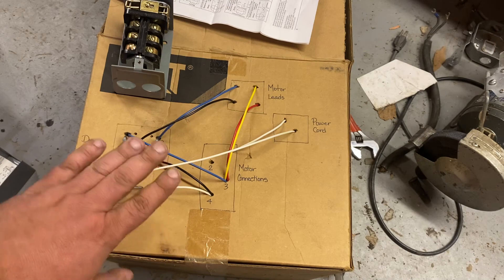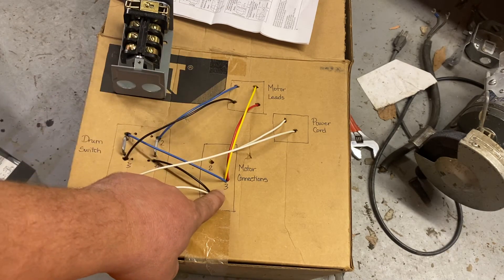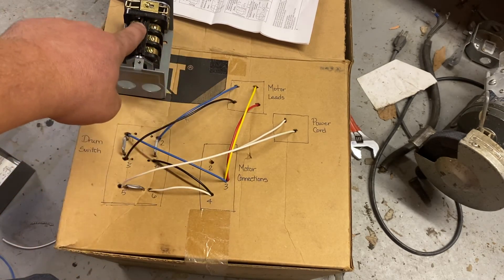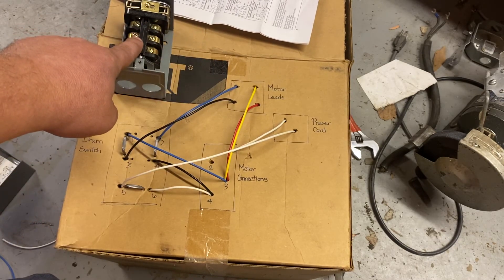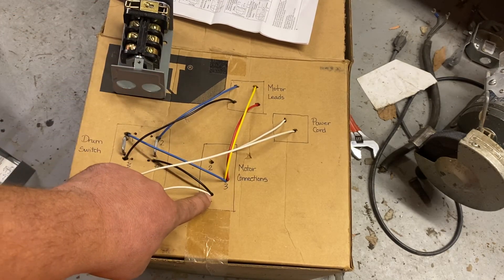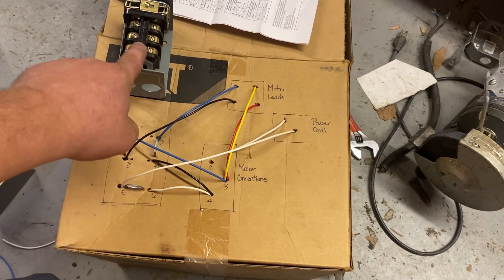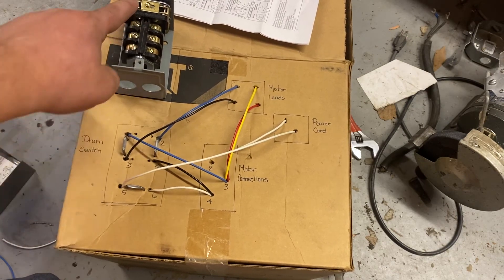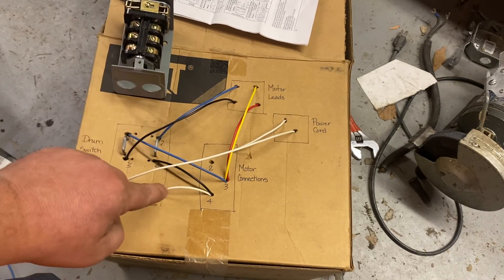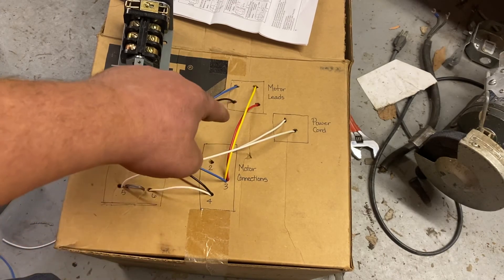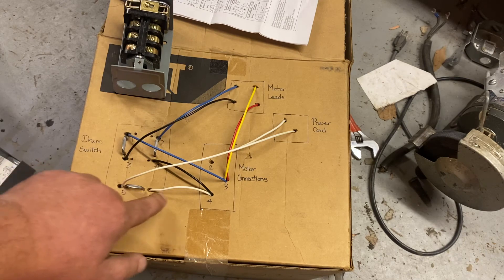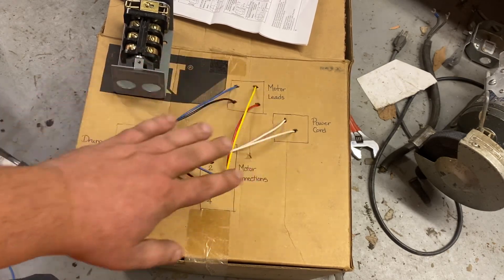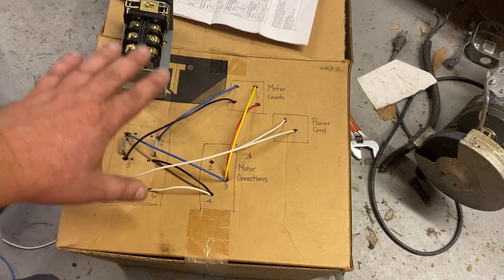So to recap, these ones are solid from the motor to the motor connections. These two wires will run to the drum switch. One power wire will run to the drum switch, and then from the drum switch out, there'll be the power wire that's broken right here. These two wires will go here, either side. That black wire will go there, blue wire there. Then opposite, black wire there, blue wire. And the other power wire is going to go there, and this other power one will be directly to terminal one on the motor. So we'll be breaking this leg to get the motor to run.